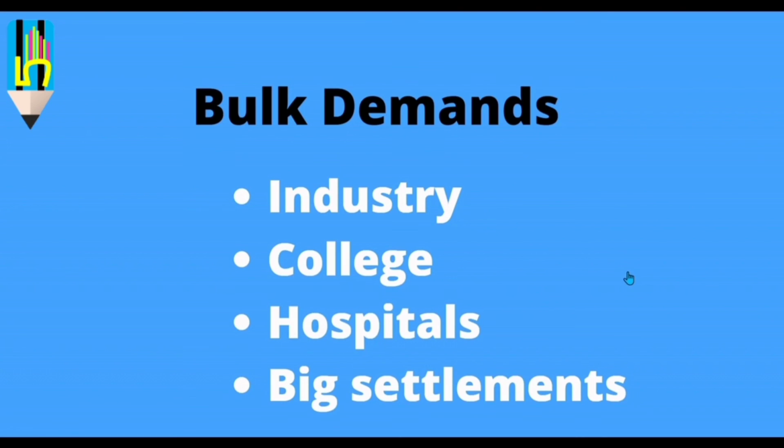Now why is it important to consider such things? The simple reason is that if we don't keep a demand at the place where it is located, the demands will be distributed in an average manner. That will give us a very incorrect size of pipes passing through that area. So if in WaterGems we keep all the bulk demand points at the exact same place where they are located in the real field, this will erase the problem and give us a correct estimate.